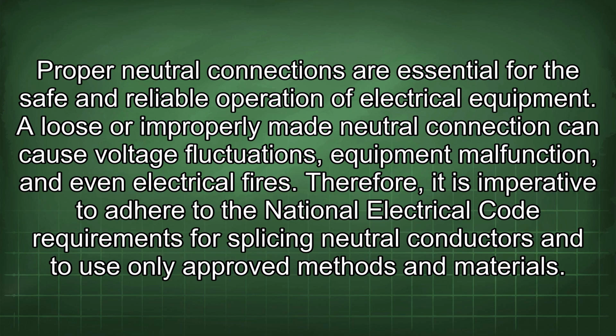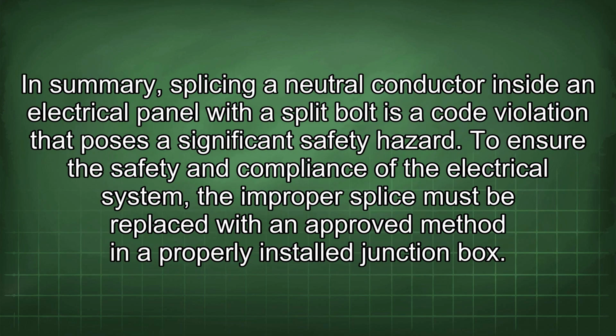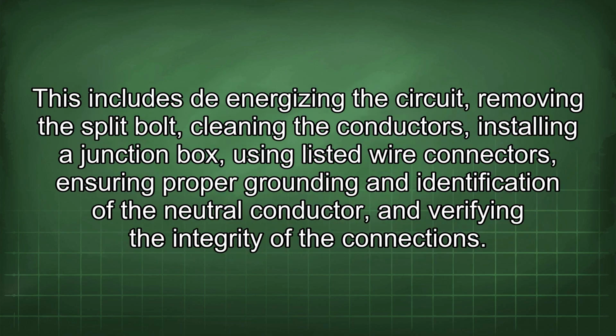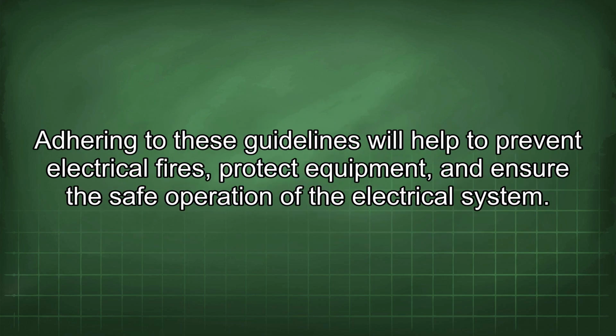In summary, splicing a neutral conductor inside an electrical panel with a split bolt is a code violation that poses a significant safety hazard. To ensure the safety and compliance of the electrical system, the improper splice must be replaced with an approved method in a properly installed junction box. This includes de-energizing the circuit, removing the split bolt, cleaning the conductors, installing a junction box, using listed wire connectors, ensuring proper grounding and identification of the neutral conductor, and verifying the integrity of the connections. Adhering to these guidelines will help to prevent electrical fires, protect equipment, and ensure the safe operation of the electrical system.